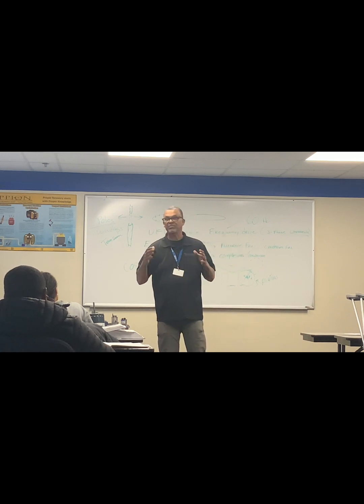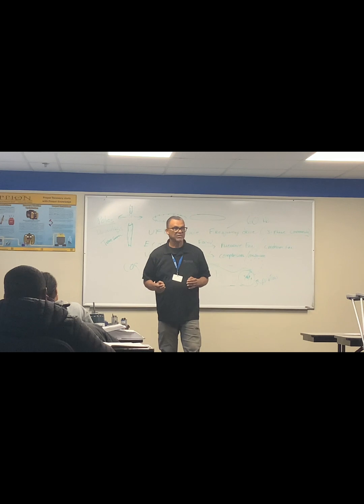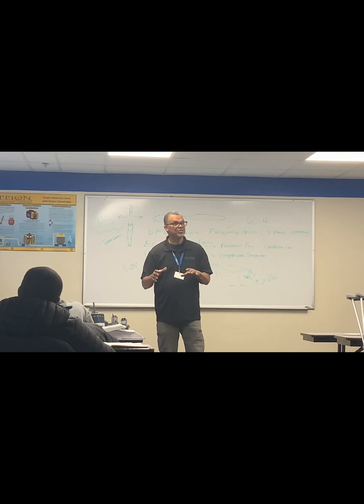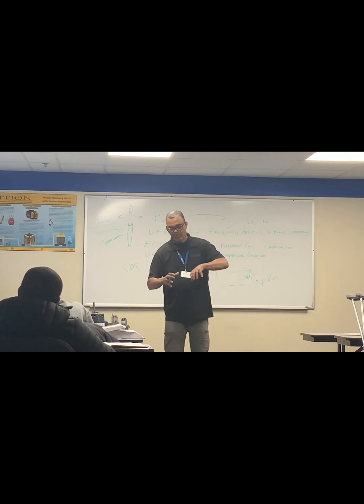So if I have a distribution wheel that skinny or 8 inches, you're only gonna get so much air out of there. But it must be a very small system if you're trying to heat this room up. If I need more, that wheel's gonna start getting wider and bigger, because you have to deliver more, and the motor's gonna be bigger. It's gonna be mounted on the side, as we'll see in the lab, mounted on the side of the frame of the distribution assembly, and it's gonna have 3 screws in it to hold it in place, and the motor will go in the middle of it, and then the shaft will go into the air distribution wheel, so it'll be locked in there and balanced.